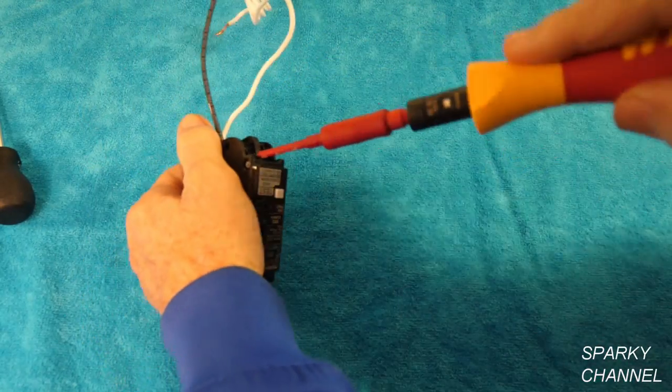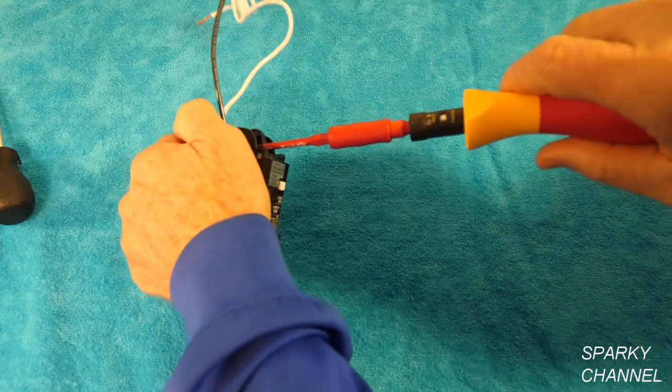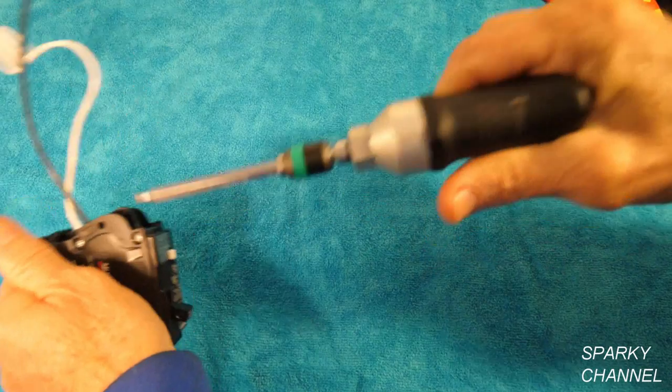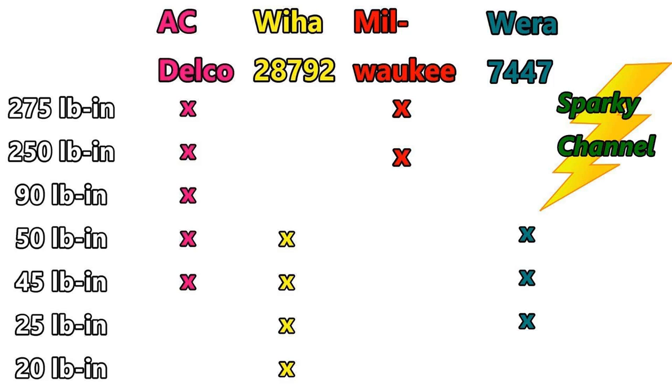Here's my Wiha insulated torque screwdriver and I will be setting it to 25 pound inches for the Murray circuit breaker. Here's my Wera torque screwdriver with the same breaker. I own four torquing tools and I made up a little chart here.